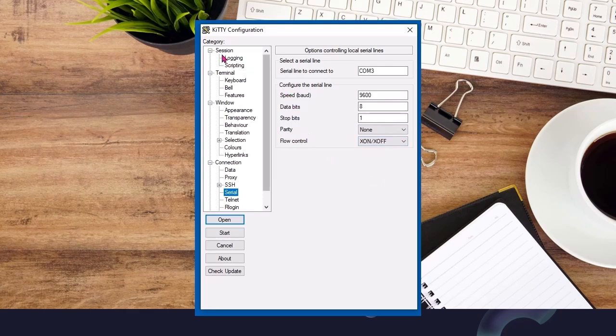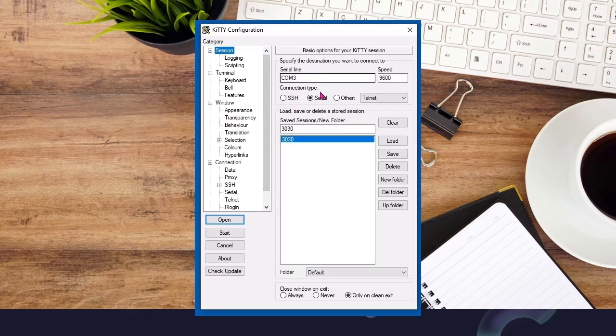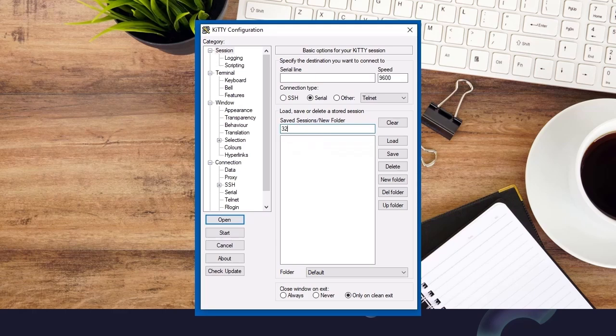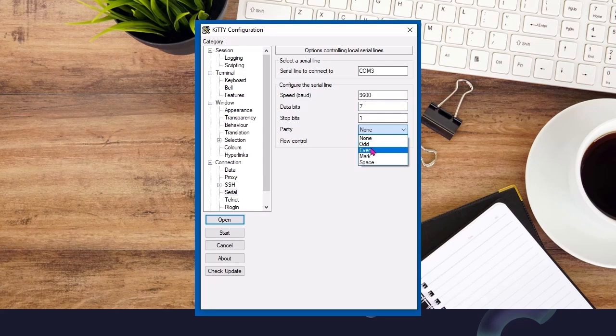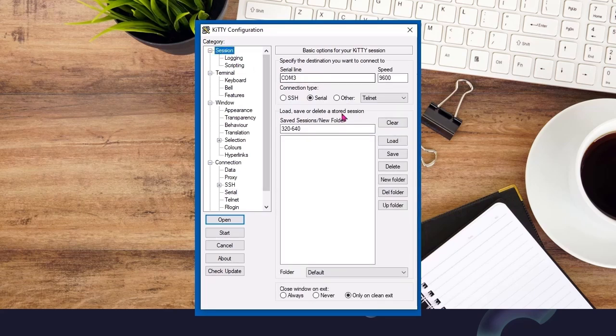We can create another one for the 320 and 640 panels. Again, it's going to be COM3. And under the serial, we're going to need to change this to 7 bits, and the parity is going to be even. So go back there, save that, and then you'll be all set.